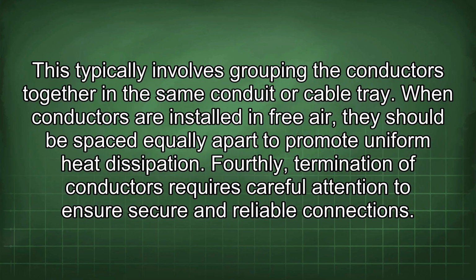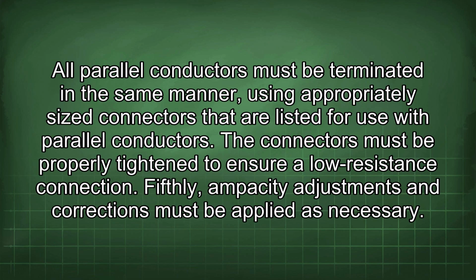Fourthly, termination of conductors requires careful attention to ensure secure and reliable connections. All parallel conductors must be terminated in the same manner, using appropriately sized connectors that are listed for use with parallel conductors. The connectors must be properly tightened to ensure a low resistance connection.